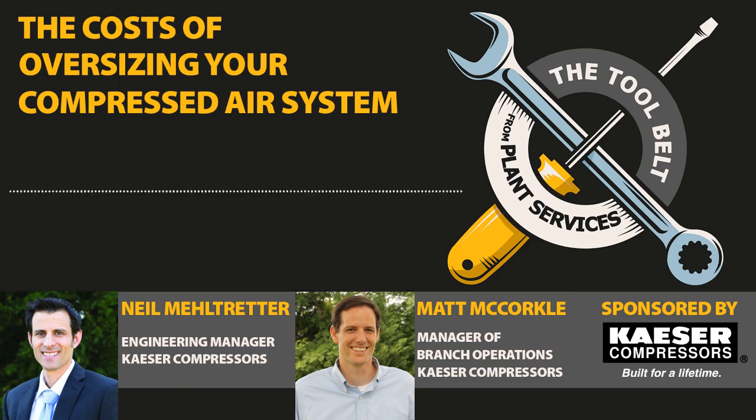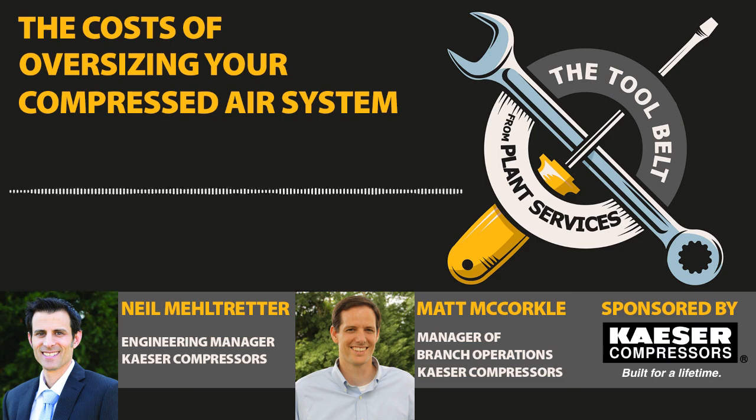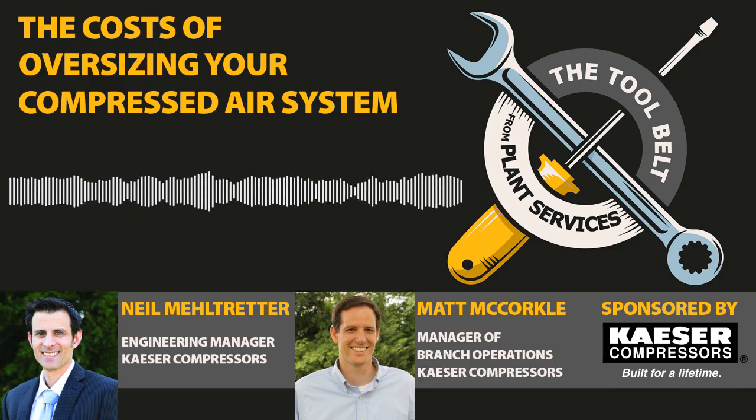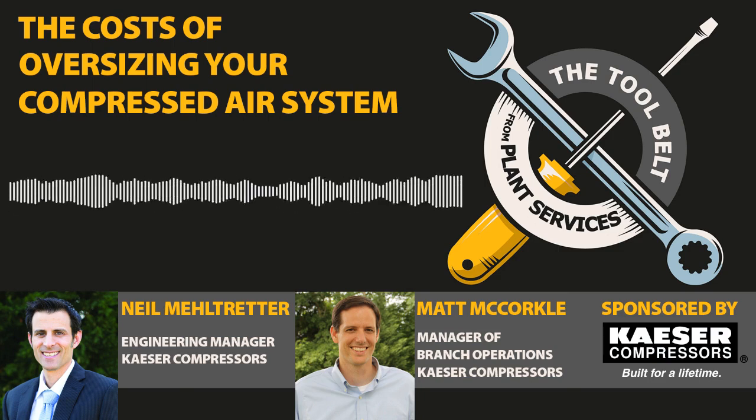And then, really, what's your leak load? In a lot of cases, Matt alluded to studies that we might do, air studies, efficiency studies, and a lot of customers are also looking at what they're doing on a daily, nightly, weekly basis to see what that leak load might be. The Department of Energy has come out with a study that we cite a lot, that 45% to 60% of all compressed air produced is going to production, which means that balance is wasted. So this will help you figure out what that waste might be.